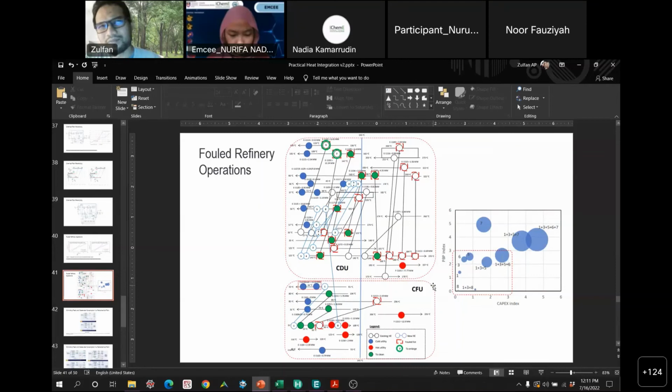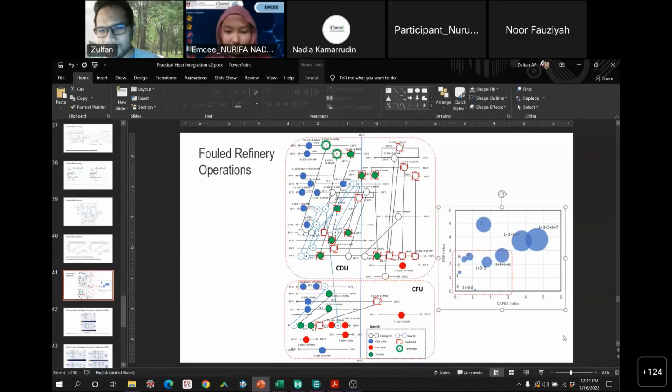And then you know that you can save, for example, 4,000 ringgits per year. So that 4,000 ringgits per year, you have 10,000 capex. So 10,000 capex divided by 4,000 per year means you will have a payback period of about 2.5 years, basically. So 10 divided by 4. That's the way we calculate a quick cost estimation of the payback period. Is that clear or not clear? Okay, I think that's clear, Doctor. Thank you. Next question.